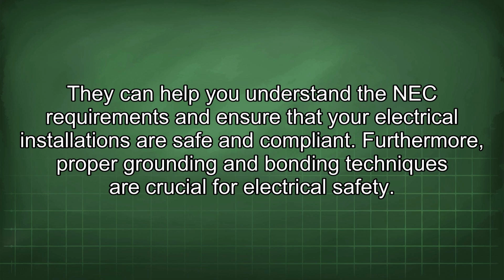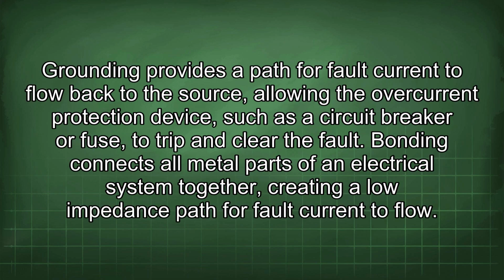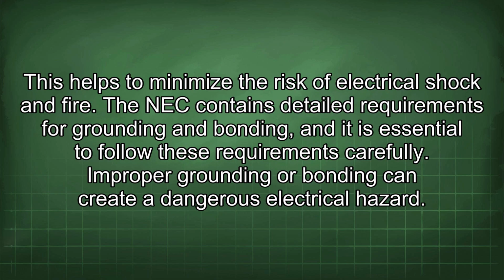Furthermore, proper grounding and bonding techniques are crucial for electrical safety. Grounding provides a path for fault current to flow back to the source, allowing the overcurrent protection device such as a circuit breaker or fuse to trip and clear the fault. Bonding connects all metal parts of an electrical system together, creating a low impedance path for fault current to flow. This helps to minimize the risk of electrical shock and fire. The NEC contains detailed requirements for grounding and bonding, and it is essential to follow these requirements carefully. Improper grounding or bonding can create a dangerous electrical hazard.